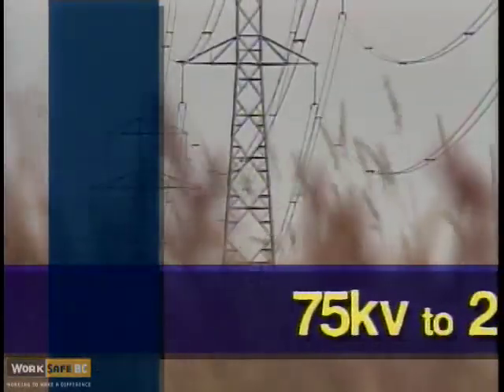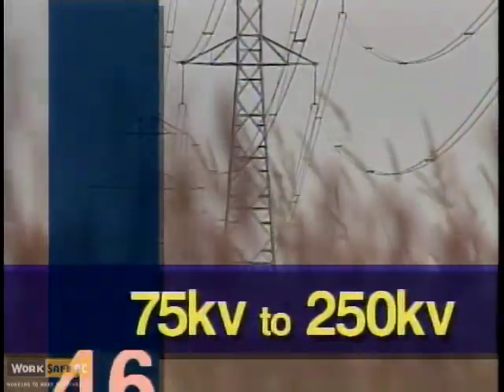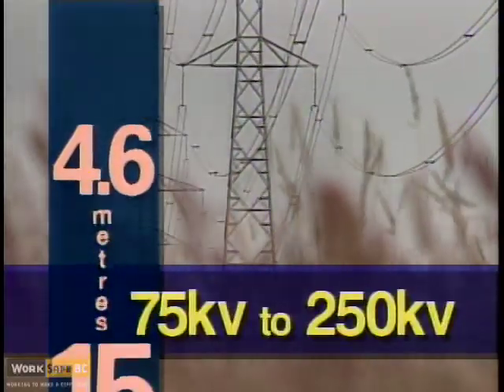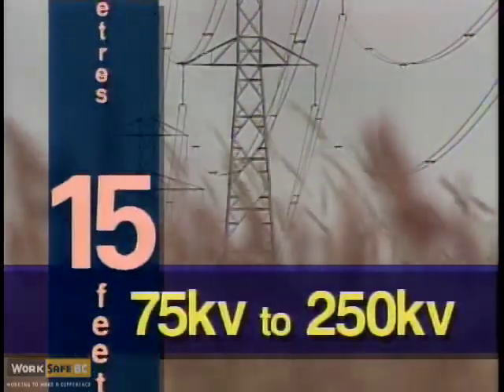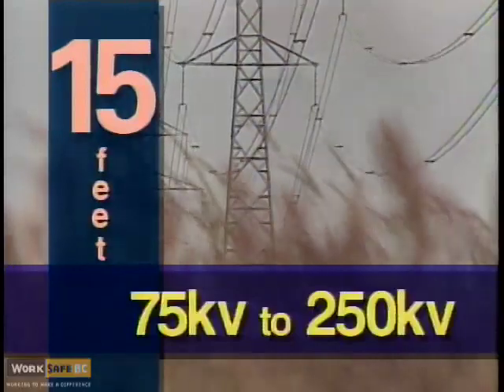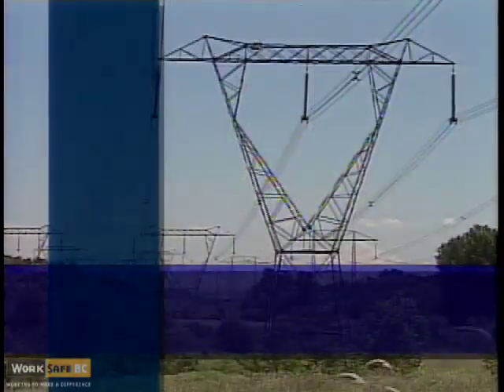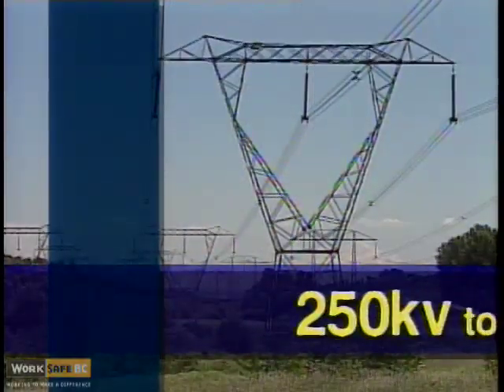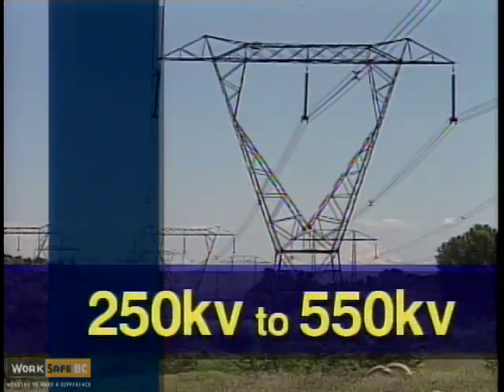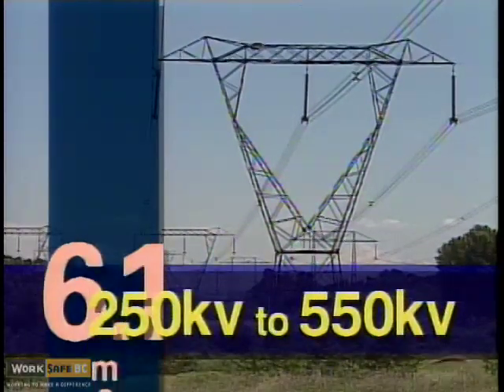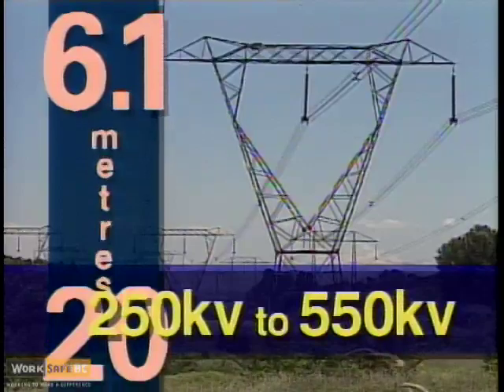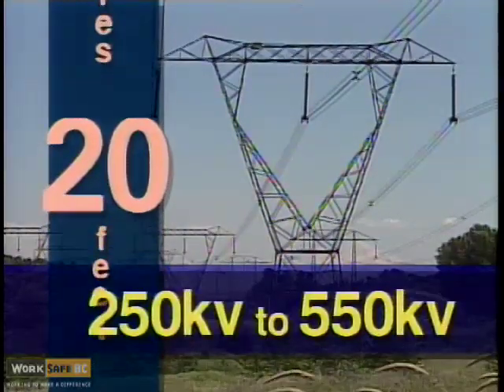Between 75,000 and 250,000 volts, increase the distance to 4.6 meters or 15 feet. 250,000 to 550,000 volts requires a minimum distance of 6.1 meters or 20 feet.